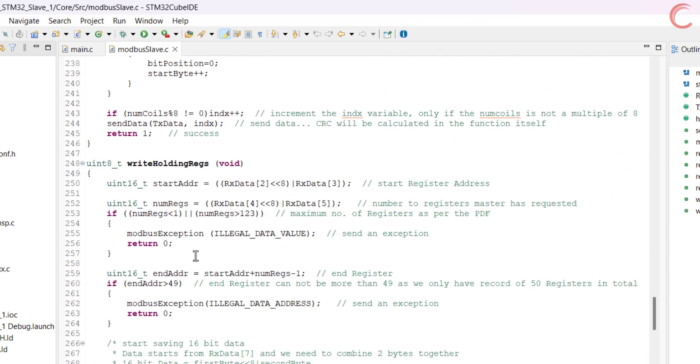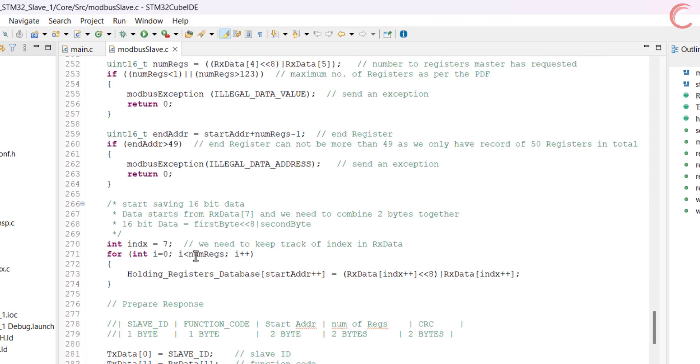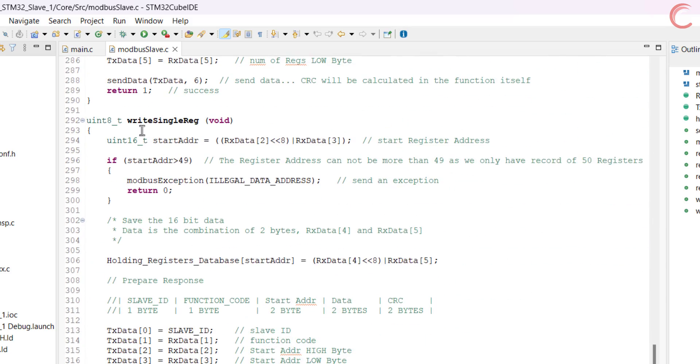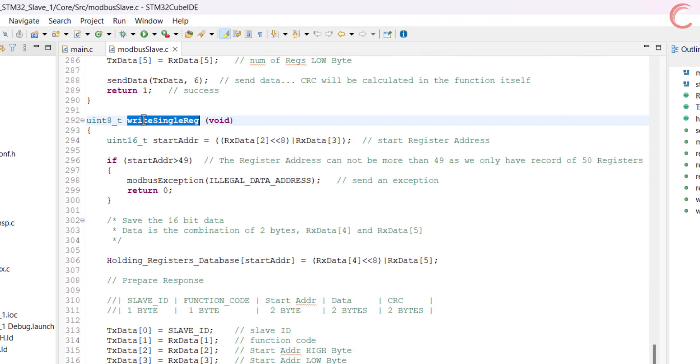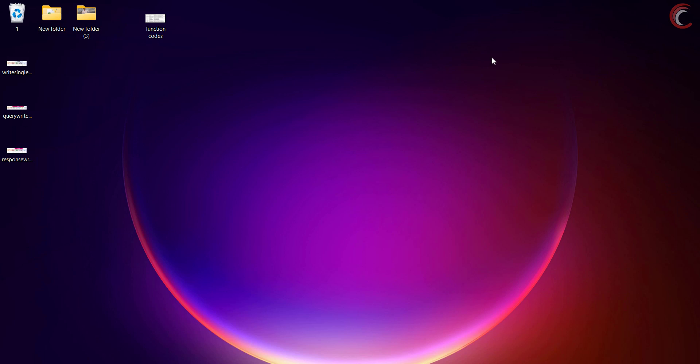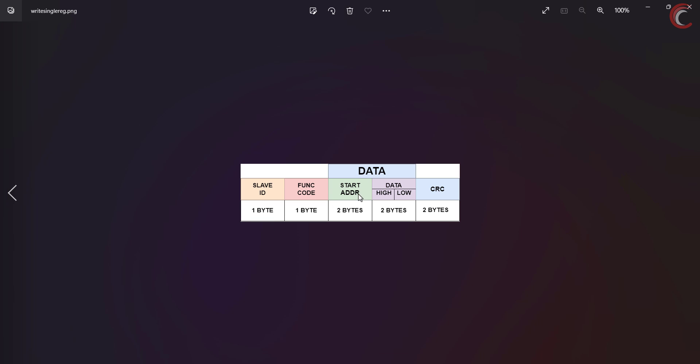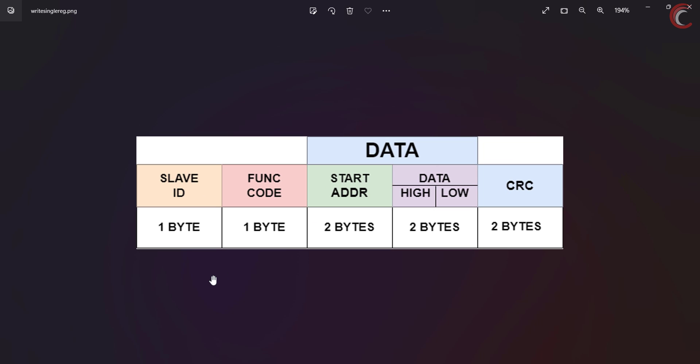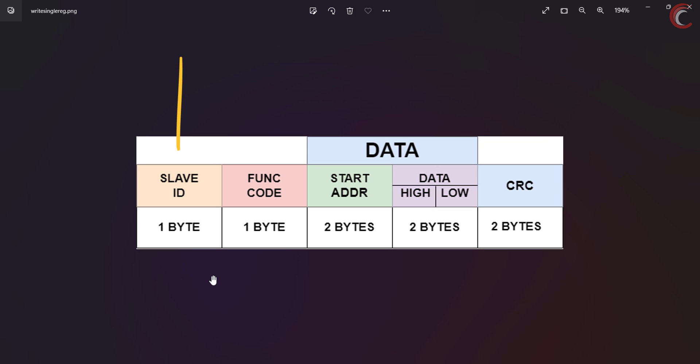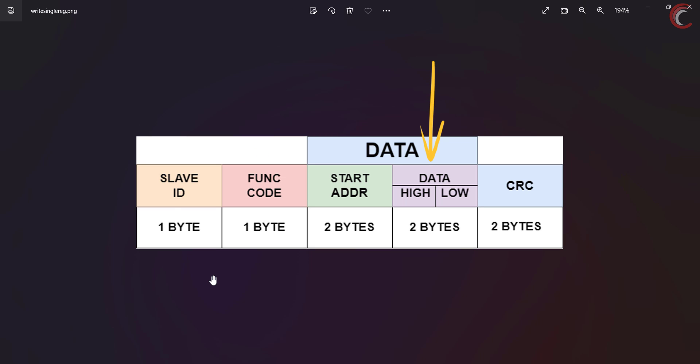Let's first discuss the single register. This is the format of the request sent by the master. It contains the slave ID, the function code, the address of the register, the two bytes of data master wants to write, and the CRC.